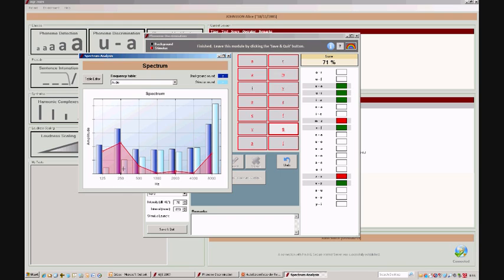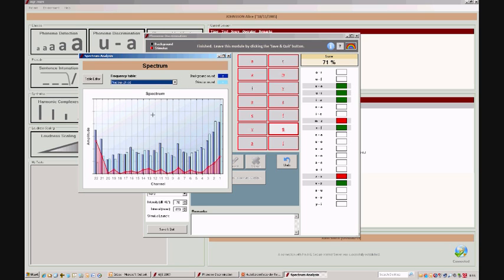You may select another frequency table, for instance the frequency table that corresponds to the device the listener is wearing. The spectral content is then displayed as a function of the frequency bands chosen. The graph now shows the channels containing the cues which the patient should use to discriminate the two sounds from one another. Here, these are electrodes 22 and 1.